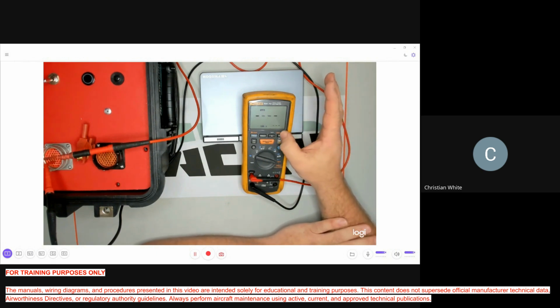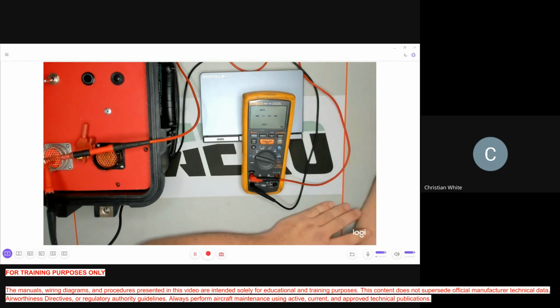I'm going to bump it up. Let's go to 500. I'm going to test our wire. Oh, 500 looks good. Well, maybe we have a good wire. Let's go to 1,000 just to make sure. Okay, I'm going to bump it up to 1,000. Oh, I'm seeing something at 1,000 that I didn't see at 500.